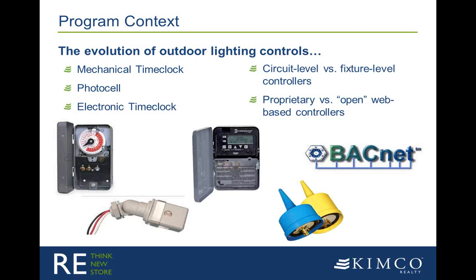You'll see the 3 components on the bottom left: the mechanical time clock, below that the photo cell, and above that an electronic time clock. These are probably your most common components used for outdoor lighting control. They're all very low cost. They're all easy to install. The cons would be that they are all prone to user errors, both in terms of the initial setup as well as the ongoing operation. They're all prone to getting out of calibration over time, and none of them offer a remote connection for real-time monitoring or control of the lighting system.